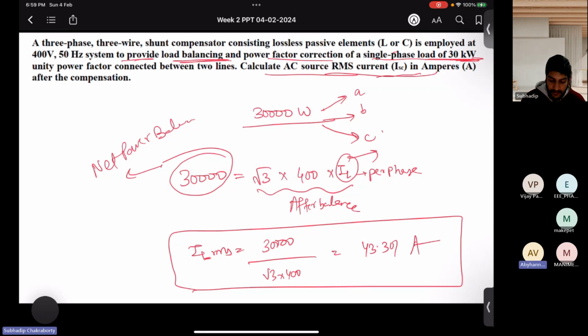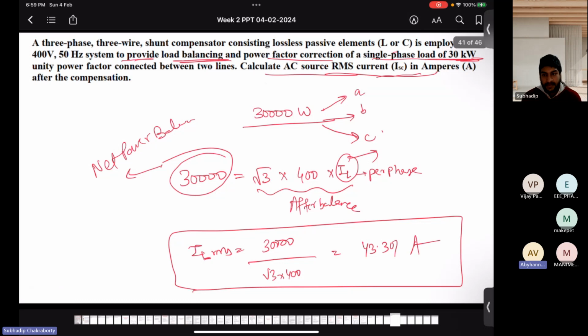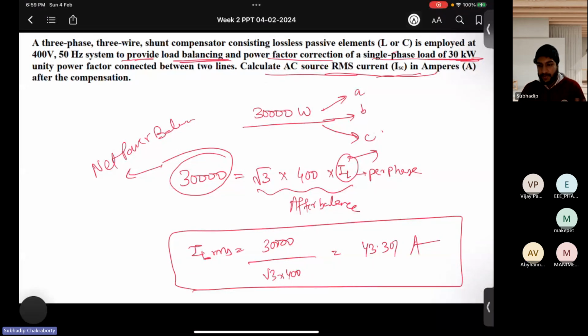Right? So one doubt. Here it is written as a single phase load of 30 kilowatt. Why are we again dividing it by 3 per phase? No, we have not divided by 3. It is the total load. What is the total load? When you use compensation, or even when you don't use compensation, load will be 30 kilowatts only. No matter whether it is connected among 2 lines or 3 lines or whatever, net loading before and after compensation on the system will be 30 kilowatts.